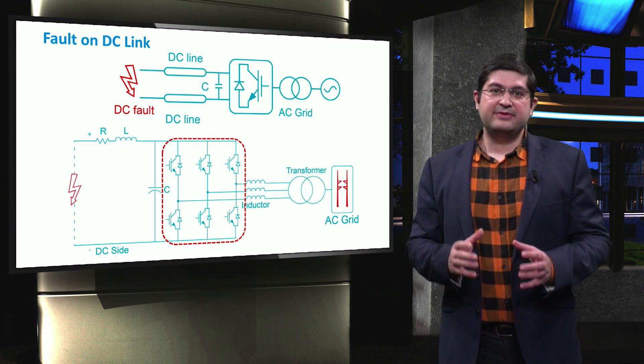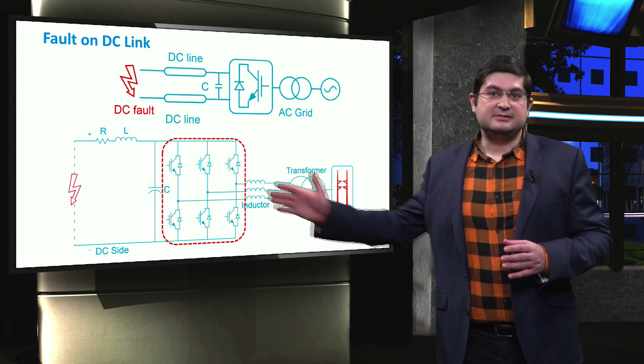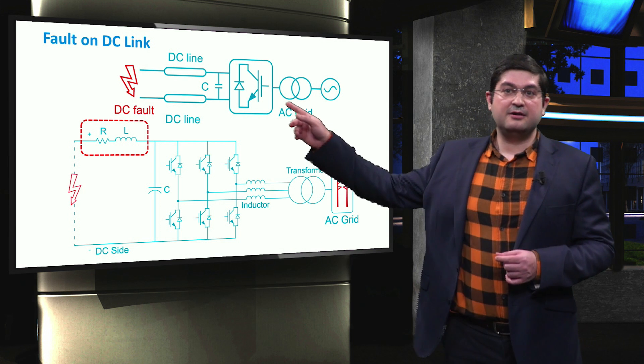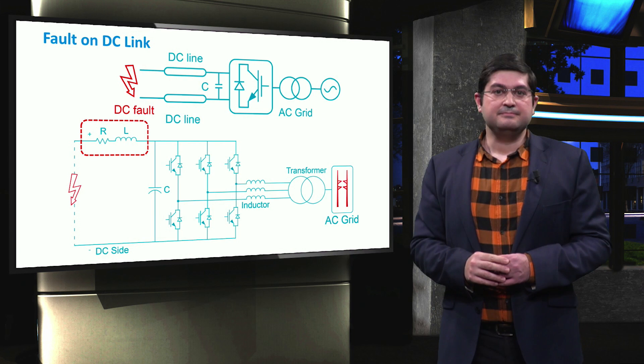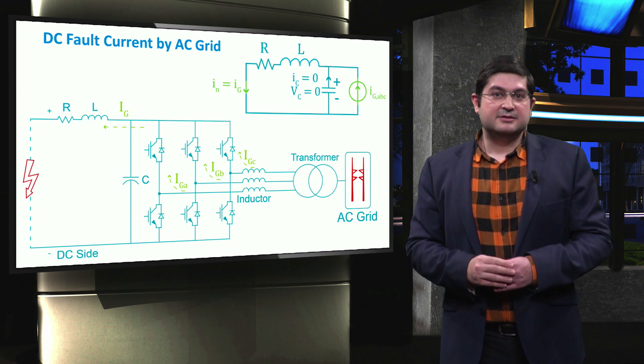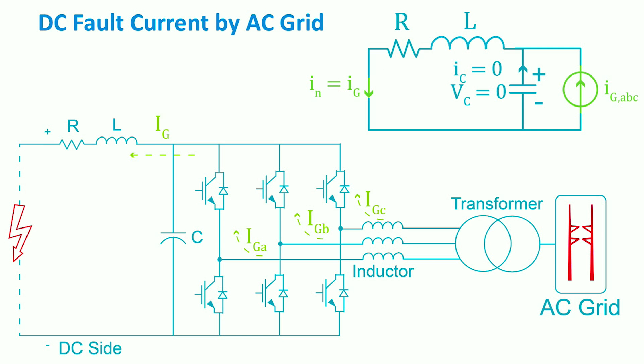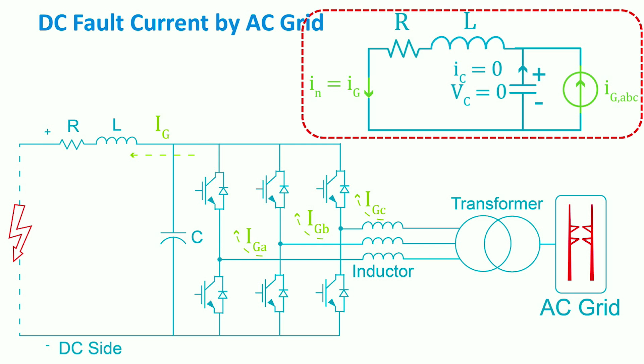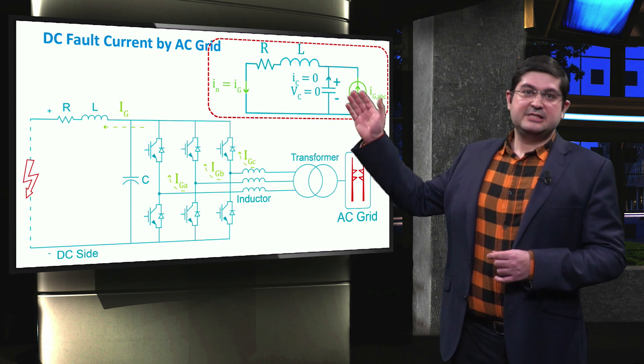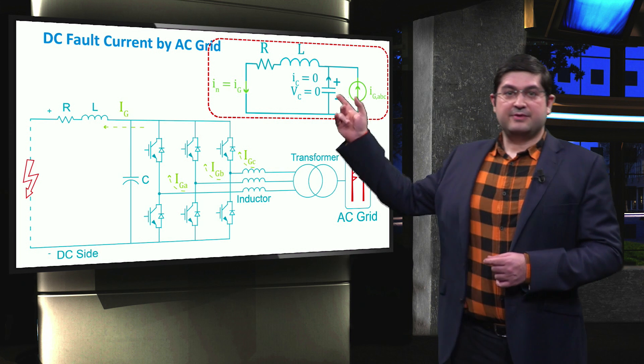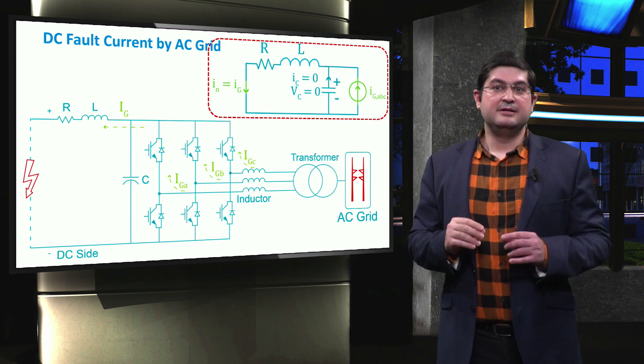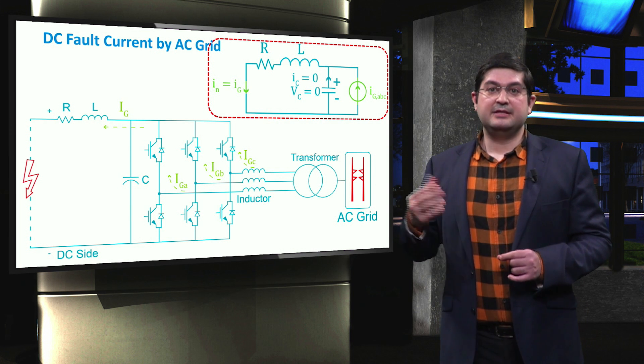Here we assume that a three-phase three-leg converter is used to supply the DC side, where the line is represented by the resistance R and the inductance L. During the fault at the DC side, various elements contribute to the fault current. The first evident element is the grid, where the currents of phases A, B, and C pass through the electrical switches and the freewheeling diodes. The simplified equivalent circuit shows the grid represented by a current source, shown in green. In this equivalent circuit, we do not consider the current and voltage of the capacitor, as it is described in the next slide.